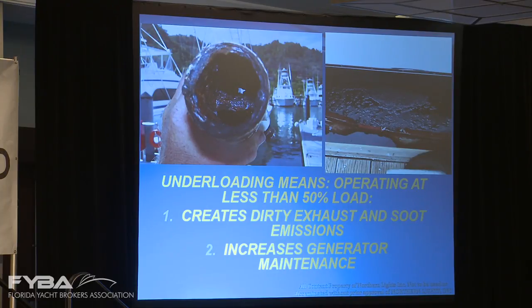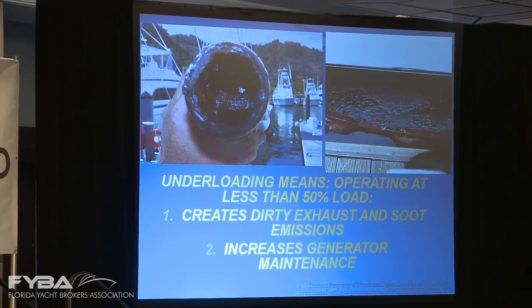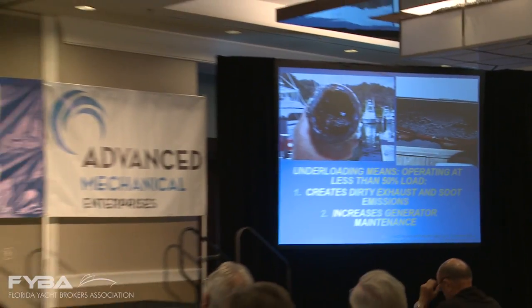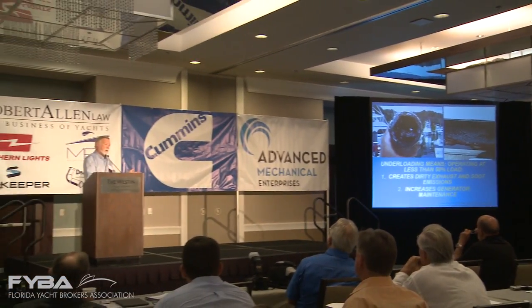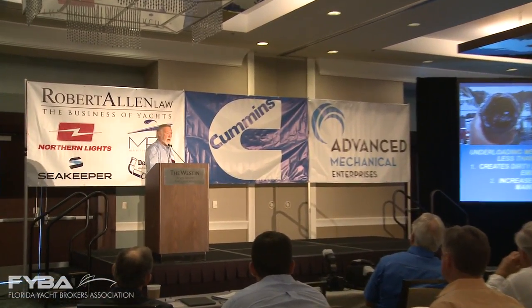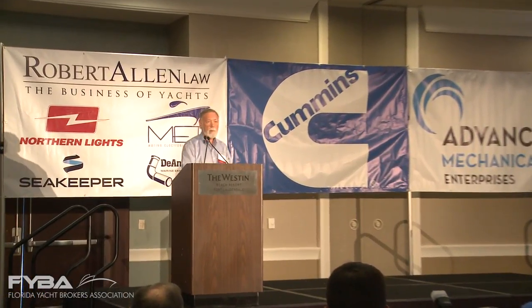Low loads are a big issue. And basically, generators are designed to carry the heavy loads. Light loads should be carried by inverters or by a smaller generator, and heavy loads are carried by a generator, okay? So the main generator is designed to be 50% loaded or more. We're doing our best to convince the boat builders to go smaller now rather than too big, because we have so many problems directly related to underloading.